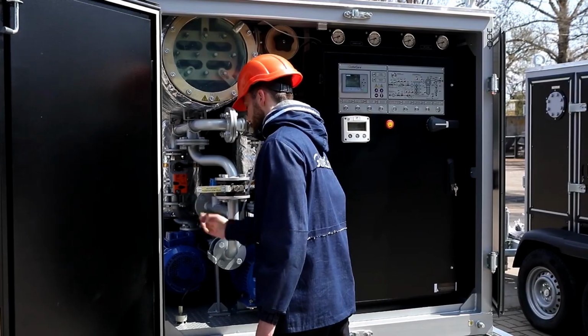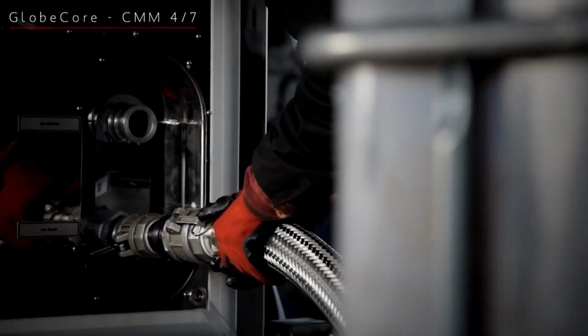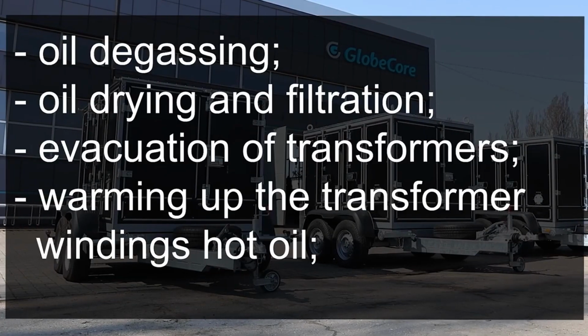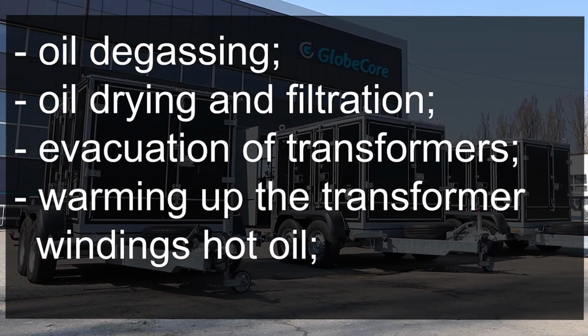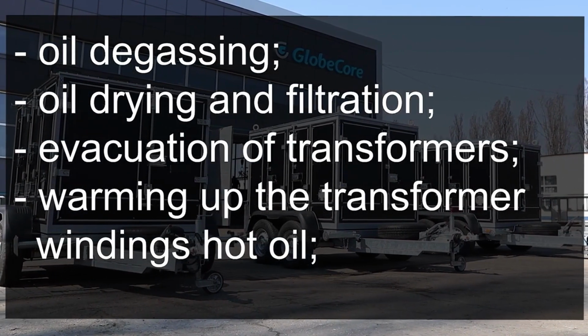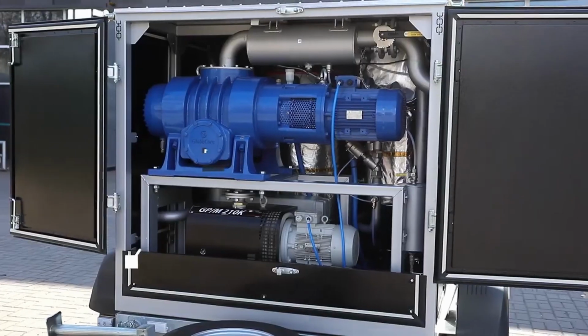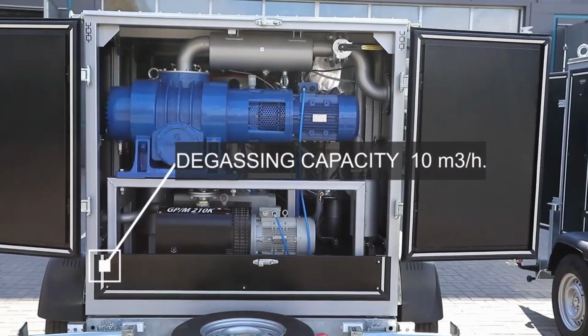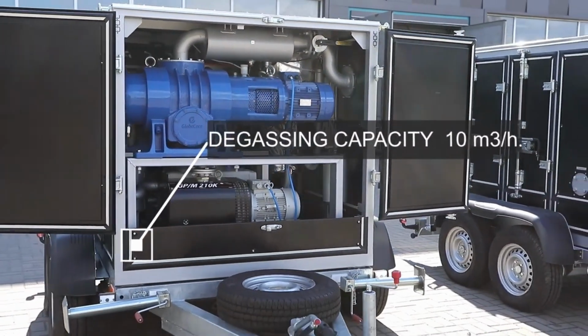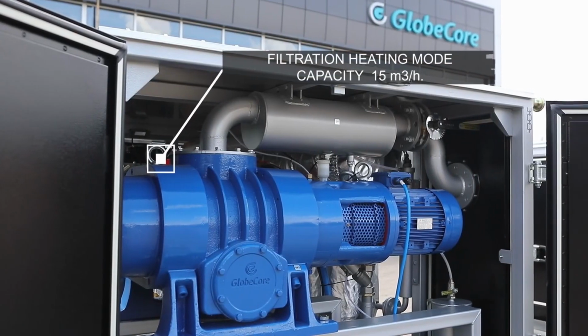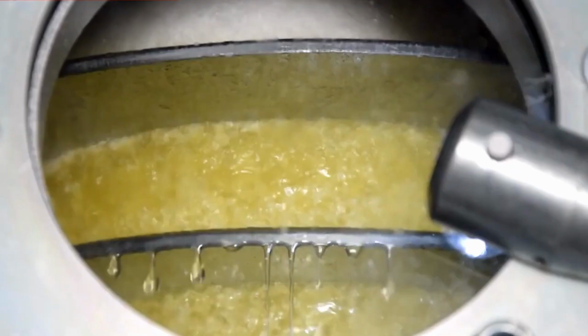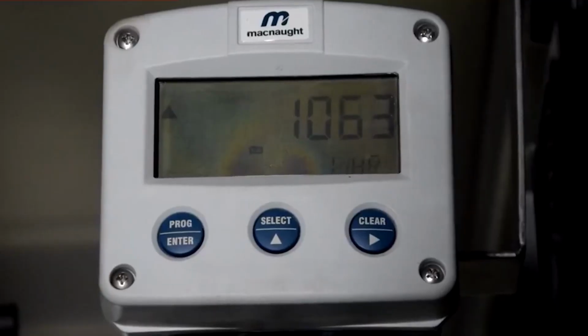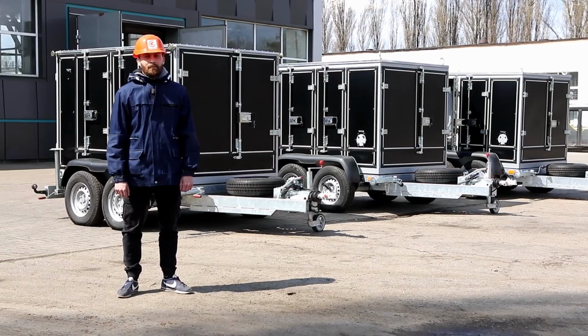One person who operates the CMM-10-15 unit can use it to carry out the following processes: oil degassing, oil drying and filtration, vacuumizing of transformers, and warm-up of transformer windings with hot oil. The capacity of the unit in degassing mode is 10 cubic meters per hour, and in heating and filtration modes is 15 cubic meters per hour.